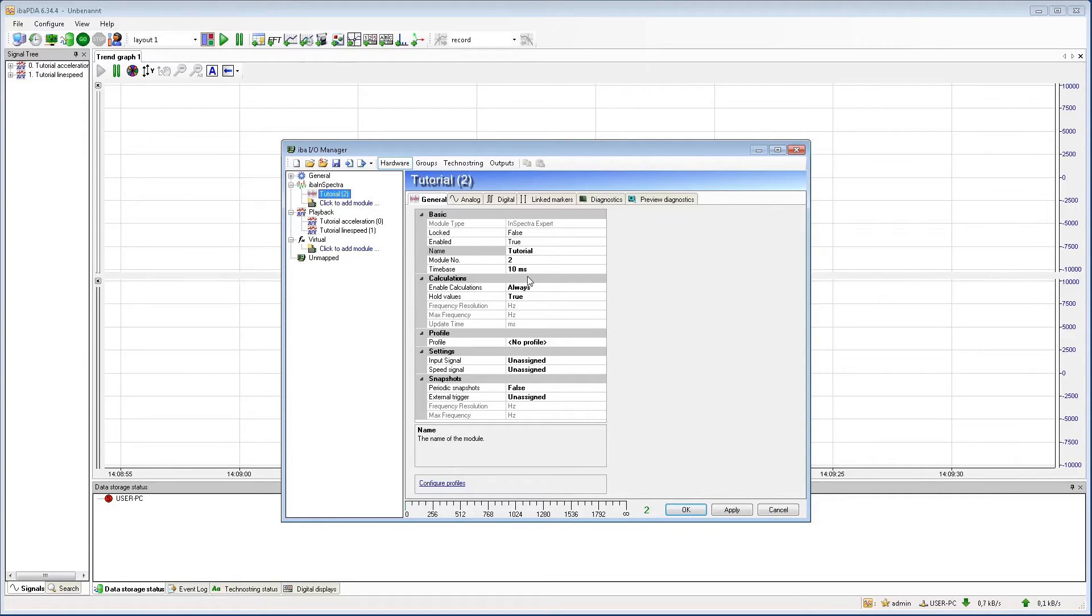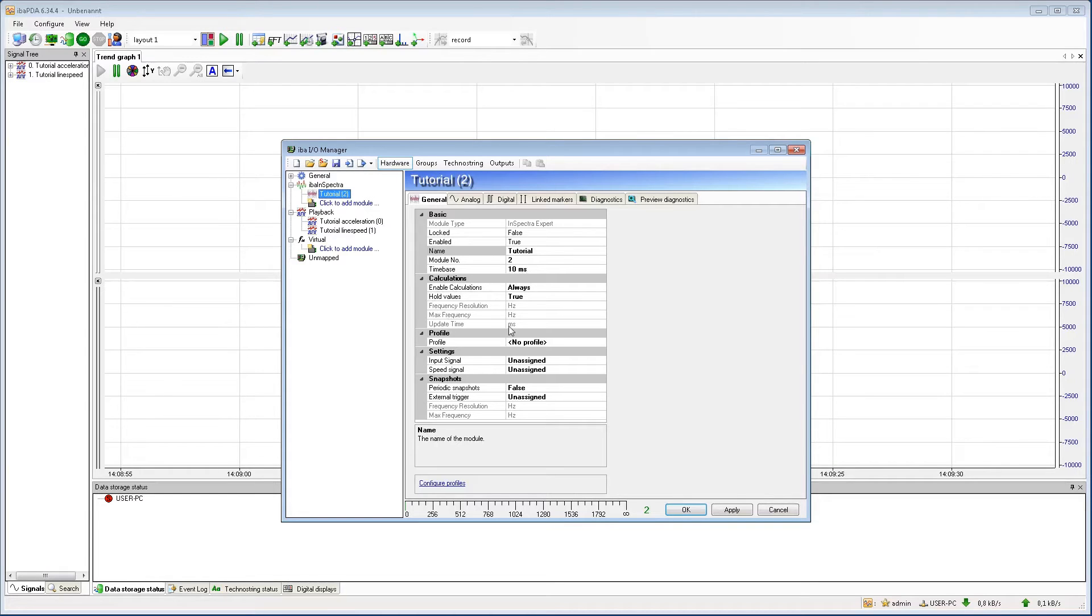Please notice that you can use a higher value for the time base because this is the time base for the band results that depends on your FFT update time. The calculation part will show you the resulting FFT parameters that are depending on the input signal sampling rate and the settings in the profile.